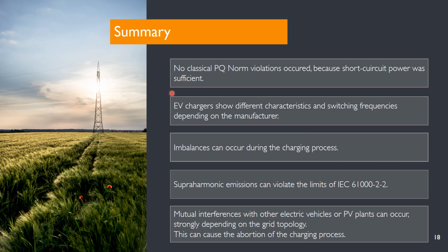All in all, I would like to give a little summary of these results. We have seen no classical power quality norm violations during the measurements, because short circuit power was sufficient for these charging stations. The EV chargers showed different characteristics in voltage and current form, but all of the mass production electric vehicles had a clean sine current wave except for the higher frequencies. We also saw some imbalances during the charging process, for example when ramping up and when reducing the charging power at high charging level. We also saw supraharmonic emission violations compared to the IEC 61000-2-2 standard. And of course, we could see some mutual interferences between electric vehicles, and also between the electric vehicle and the PV plant, which was installed on the roof of this building.